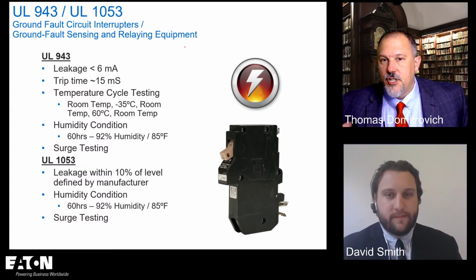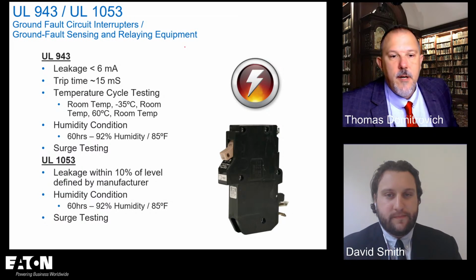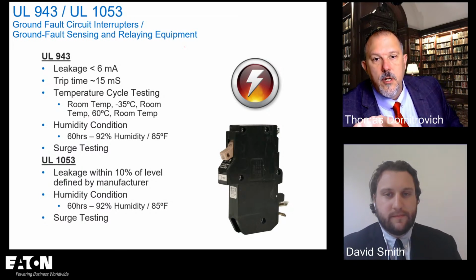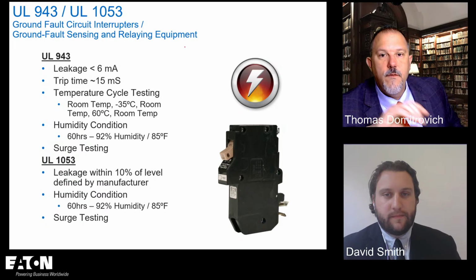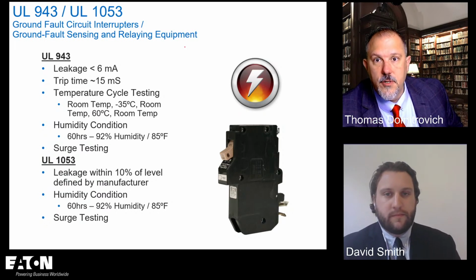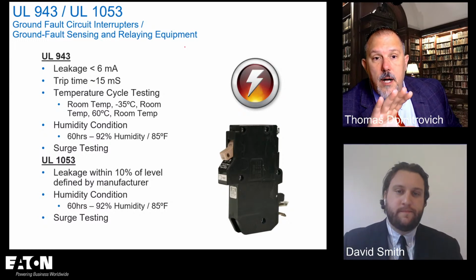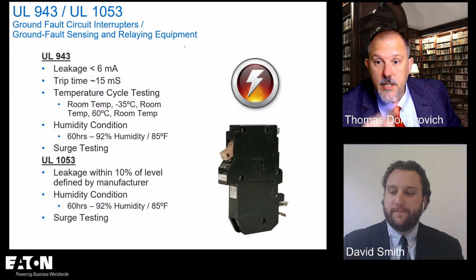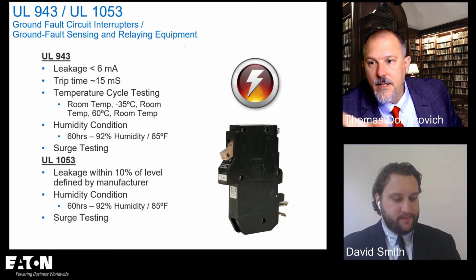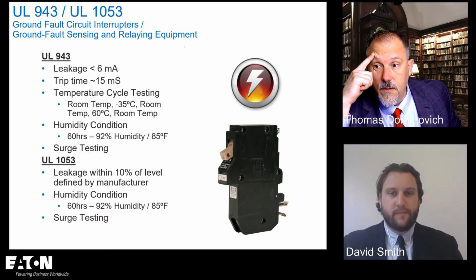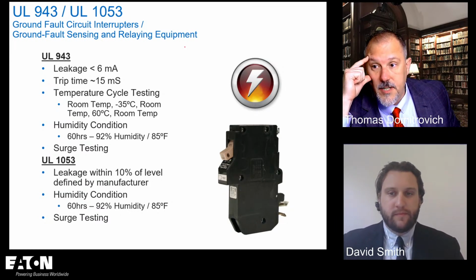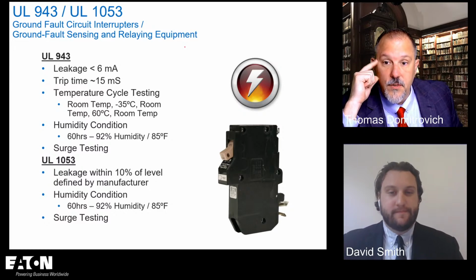It's permitted, and I'll show you. We'll take a look at the language, but you have to follow the rules in 210.12 with the length of the conductors, and we'll explain why the lengths of the conductors are there and how we came up with those numbers. But that's a good question. Yes, we're going to hit that. And so Robert says the dual function breakers versus combination AFCI breakers, people confuse them.